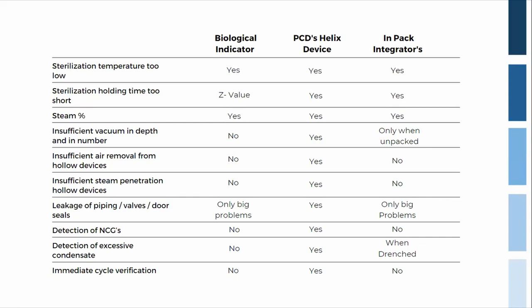The leak test is okay. The Bowie-Dick test pack is okay. The technical engineer says it's okay. The biological indicator is negative, which is okay. So only the PCD is giving a wrong result, often concluding that the indicator is not working correctly. But bear in mind, a leak test is run on an empty sterilizer. A Bowie-Dick test pack is run on an empty sterilizer. A test run by the technical engineer is run on an empty sterilizer, and your biological indicator is killed in just 0.7 minutes at 134 degrees.